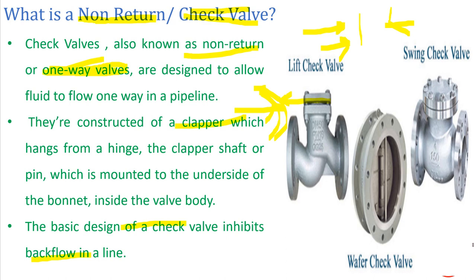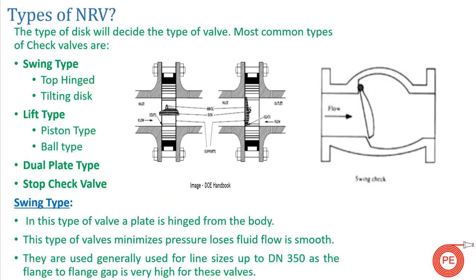The types of NRV used in the industry are: swing type — the most common, which has two sub-types: top-hinged and tilting disc; lift type — also with two sub-types: piston type and ball type; dual plate type — used when there is a space constraint; and last is the stop check valve.